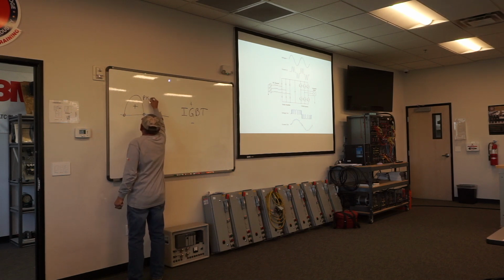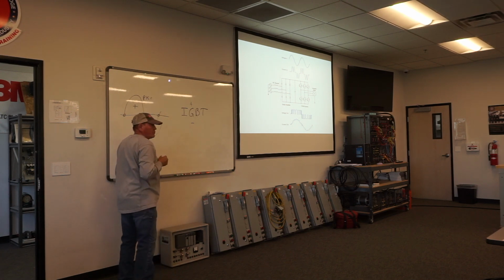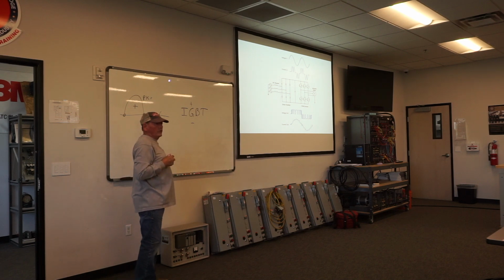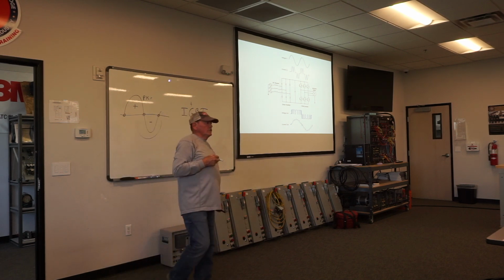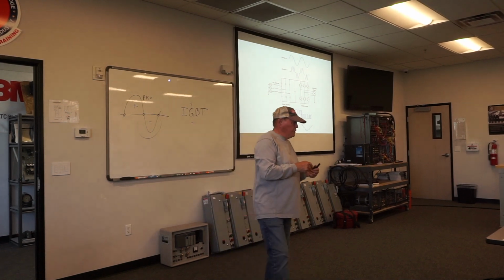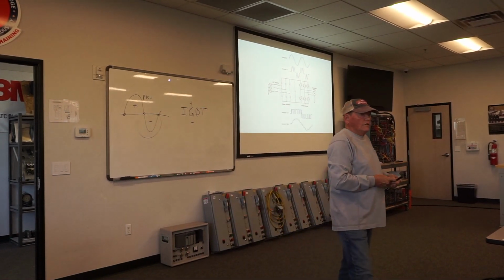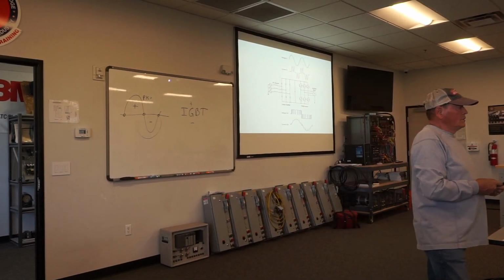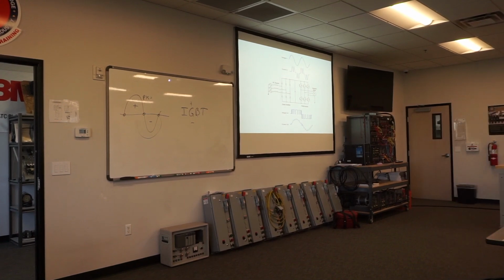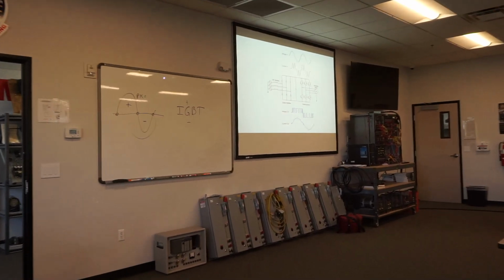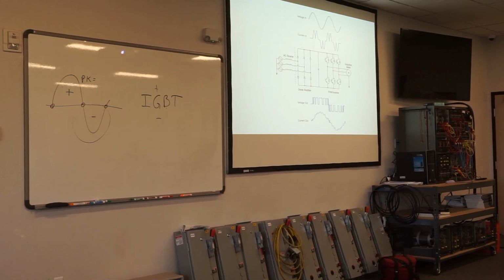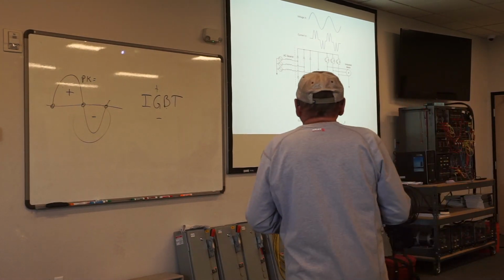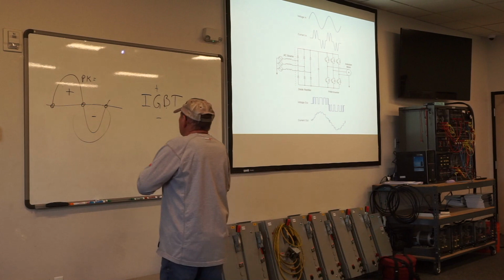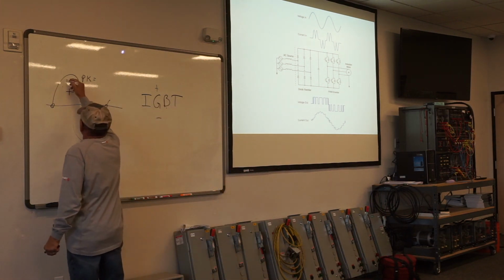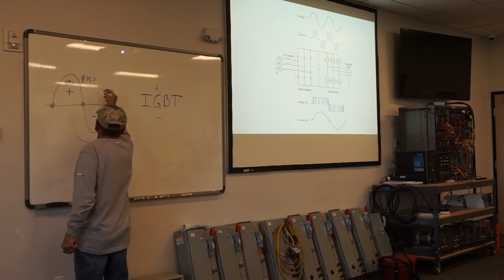Peak, right? What's the peak of 480 volts? We pull out a calculator. Give me the peak value. 1.41. We got a calculator? 683. Clint's got it over there. 683. I've got a 480 volt signal, but I have to put out 600 volts to feed that bus.